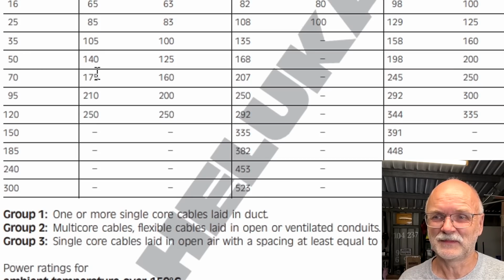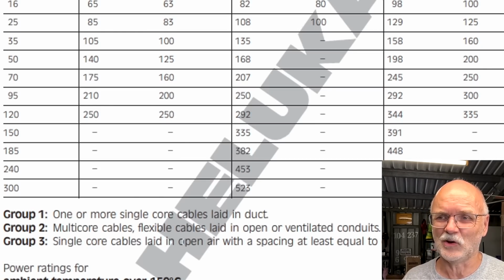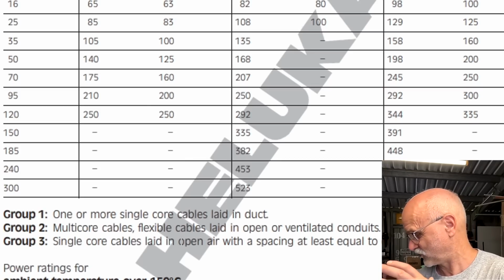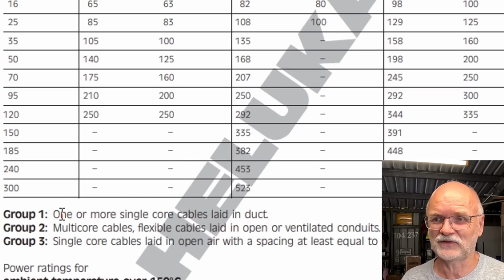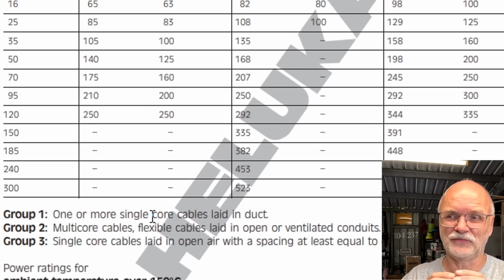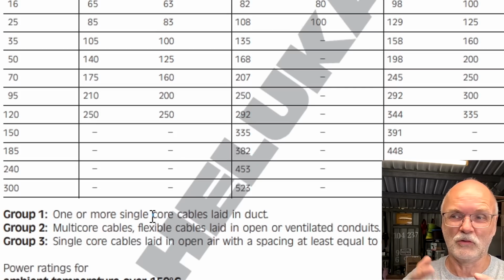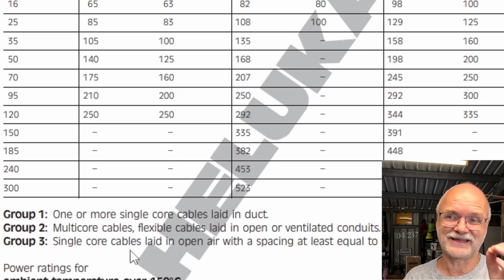So somewhere in between. One or more single core cables laid in duct. Multi-core cable, flexible and open ventilated conduit. No. Single core cables laid in open air with spacing of at least... Well, we are definitely not in open air. Yeah, it is in a closed compartment of the battery. So I would say it is group 1: one or more single core cables laid in duct. We've got an enclosure around the cables, so there's no actual airflow. The last group more implies the cables are in open air, which is not the case here.